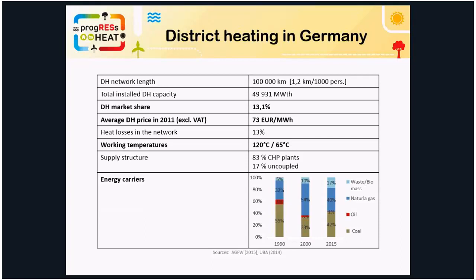So first, a few words about the district heating network in Germany. Even though in absolute values it is the largest network in Europe, in terms of market share it has around 13%, which is quite lower compared to Denmark or Sweden. The average price is around 70 euros per megawatt hour, and we are still in what's called the third generation district heating phase, with working temperatures of around 120 degrees Celsius. Based on energy carriers, many district heating networks are still supplied mostly by coal and natural gas, followed by waste and biomass. So in a way, heat pumps have quite a competitor in fossil fuels in this case.